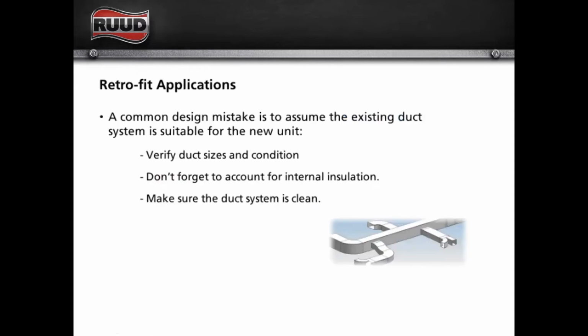In retrofit applications, don't assume that the existing ductwork can accommodate the system that you're about to put in. It's very possible that one of the contributing factors of you replacing this system is because the ductwork was not adequate, and we damaged or killed our compressor because we're not moving enough air.